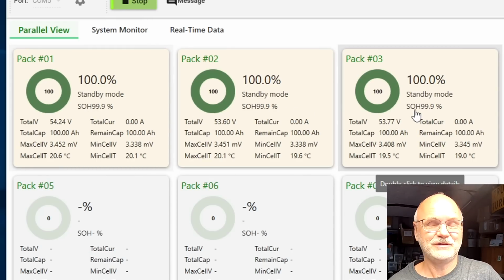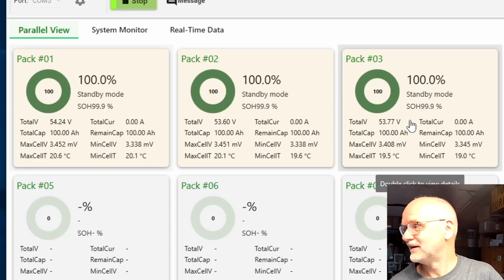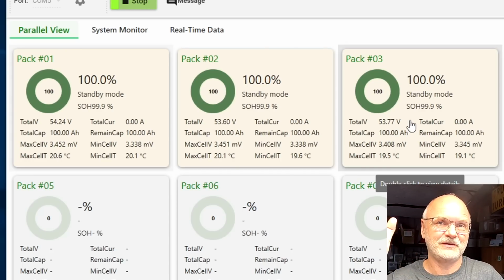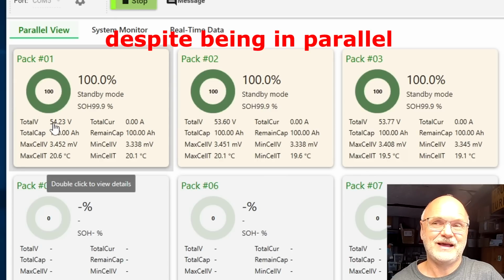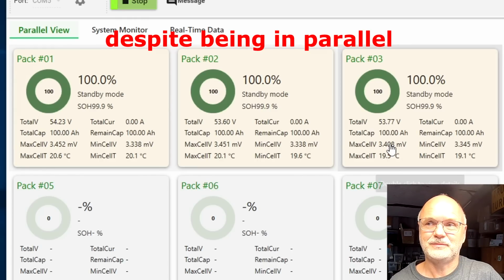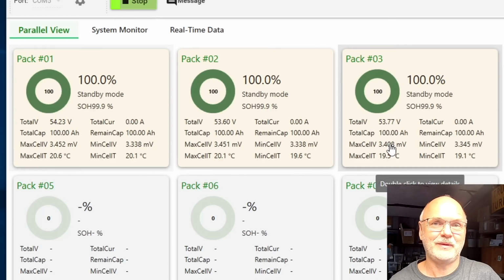How does the BMS determine that if we just do shallow charges and discharges of 70 to 100% for the last 2 or 3 weeks? We can also see the battery voltages are different, because the BMS in each of these battery banks has now turned off because of this overvoltage protection, which it's supposed to do.